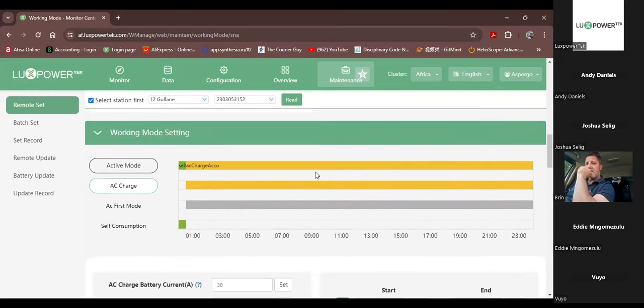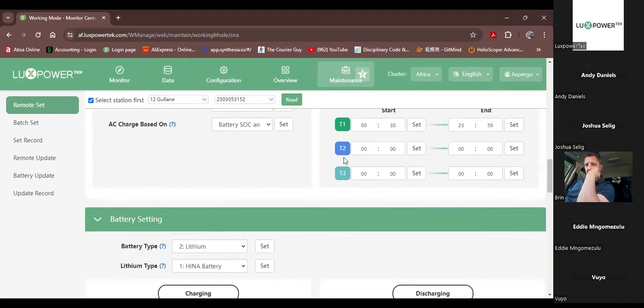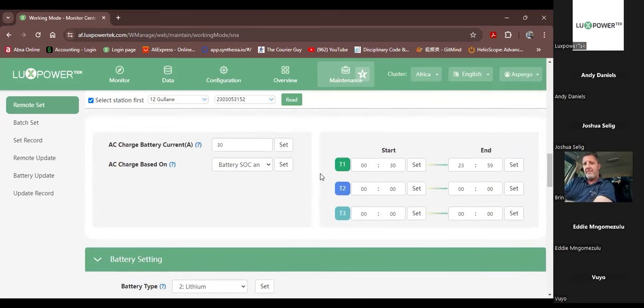Okay. You'll see that we have three different time zones here. Please don't set all three exactly the same. There's no need for that. We often see, when we go through settings and we're assisting installers or end users, that the installer has copied the settings across all three time zones. It's not necessary. You're only going to use the additional time zones if you want to use different times.